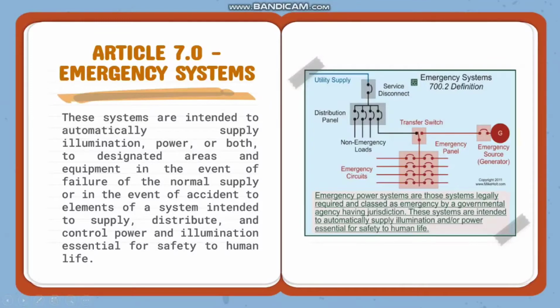So, nabanggit dito na legally required. So, ano ba yun? A system is legally required when any governmental agency having jurisdiction says it is. The rules that dictate what kinds of emergency loads are legally required are found in the locally adopted building code, such as the International Building Code or NFPA 101 Life Safety Code. So in short, emergency systems are lifelines for people, and Article 7.0 is based on keeping those lifelines from breaking.